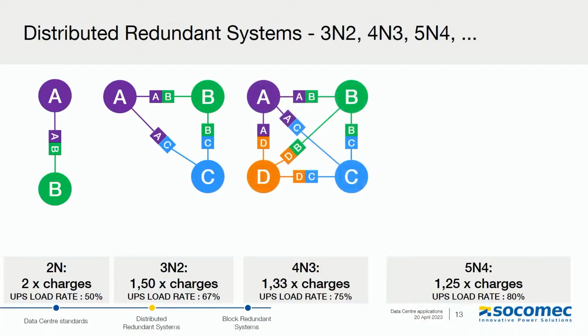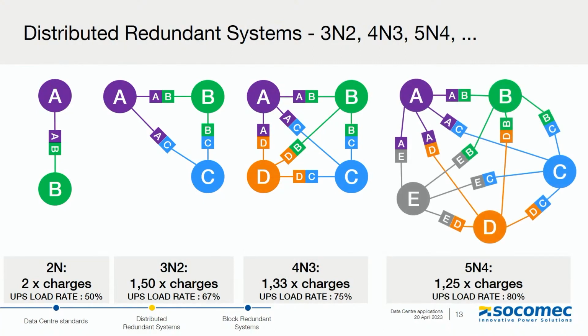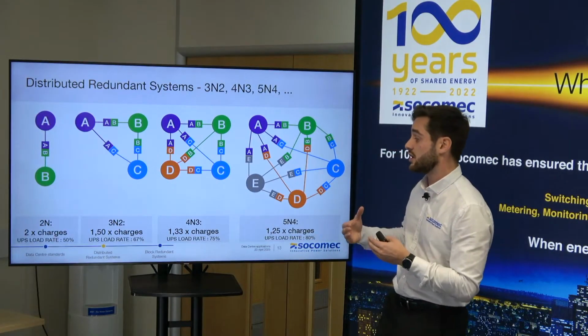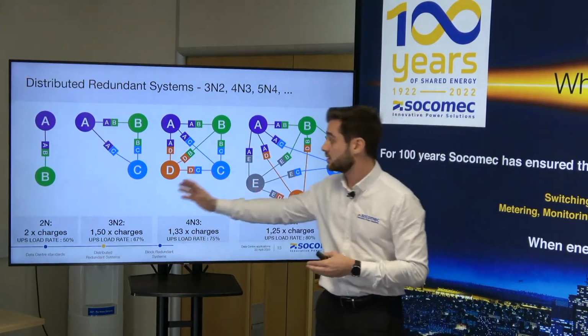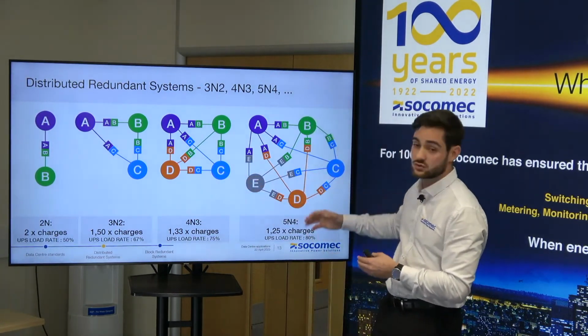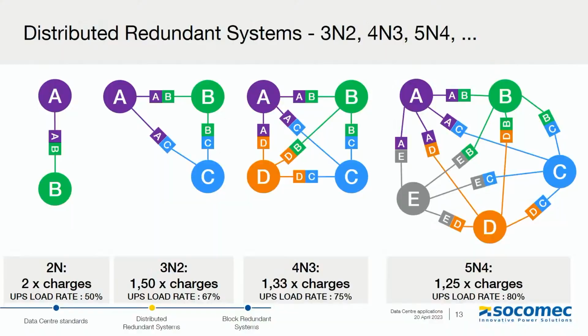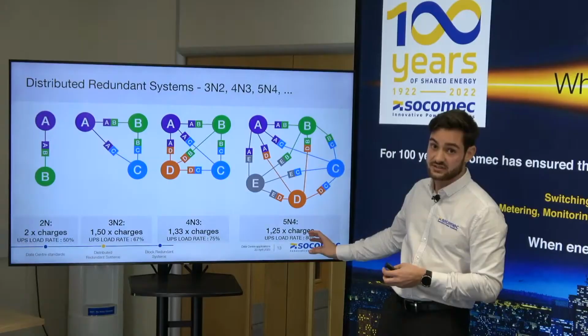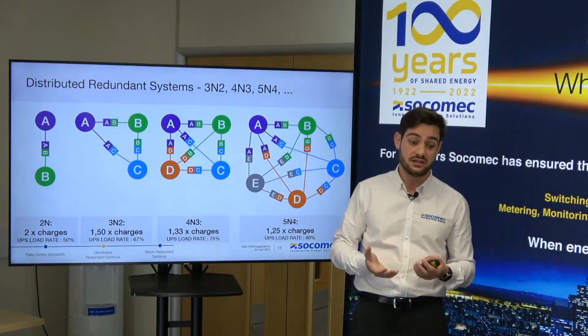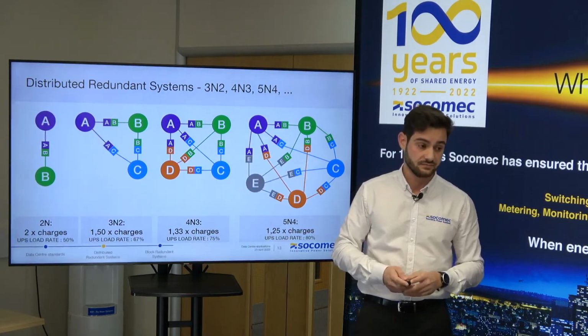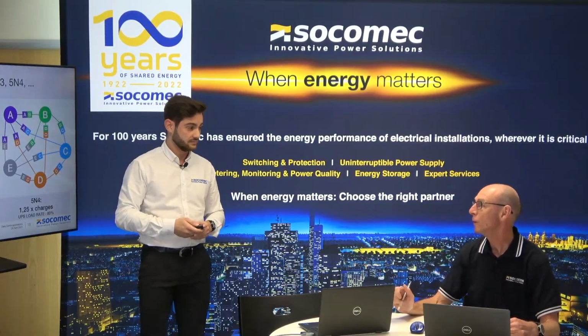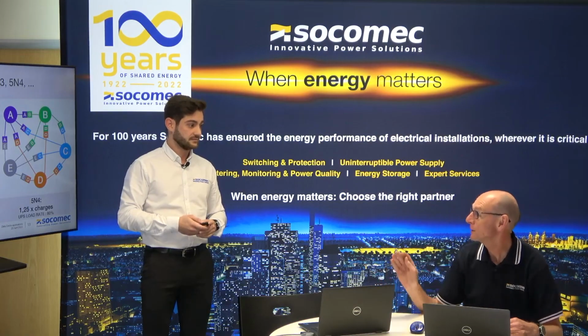So as we said, the benefit of these different solutions is to reduce the UPS size to be installed, but also we are getting closer to the UPS rating. The closer we get to the higher configurations, up to 5N4, we are increasing the UPS load rate. So we move from 50% to 80%, which can have some consequences on the efficiency of the systems. Absolutely, and obviously that's if you're looking at monolithic UPSs. If you're looking at modular UPSs, then the modules can shut down to increase the efficiency if the load isn't there. Totally right. Yeah.